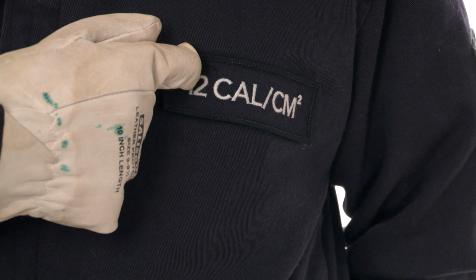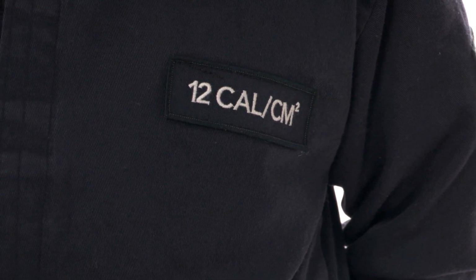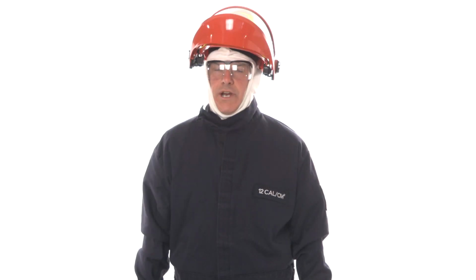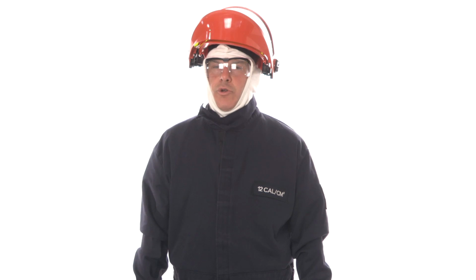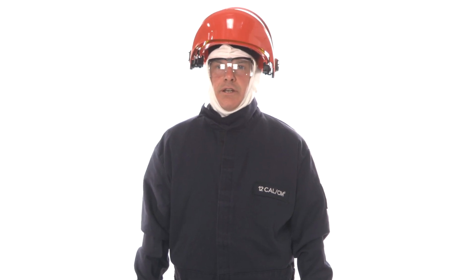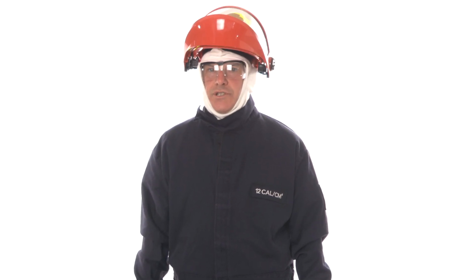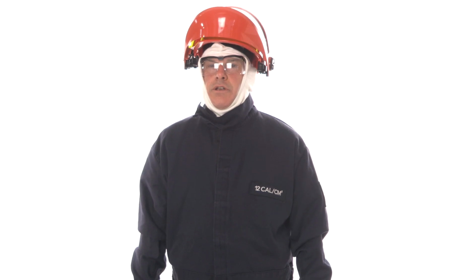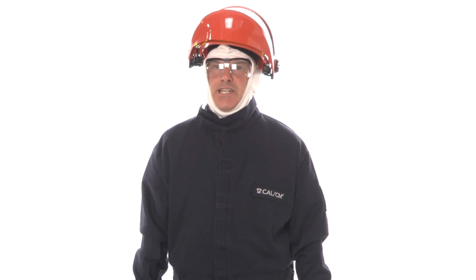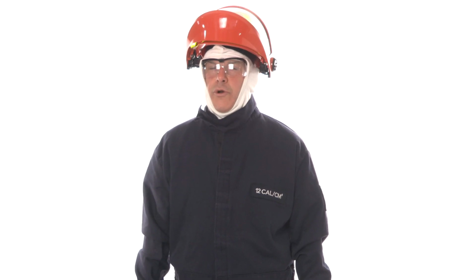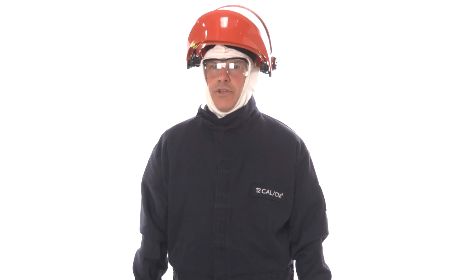Arc-rated flame-resistant clothing. Not all flame-resistant clothing is arc-rated. The clothing must be arc-rated and measured in calories per square centimeter, sometimes referred to as the ATPV or arc thermal performance value of the garment.